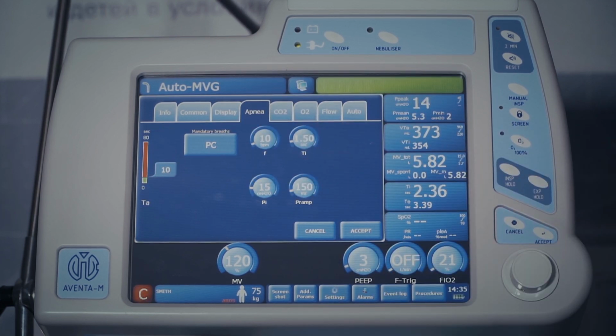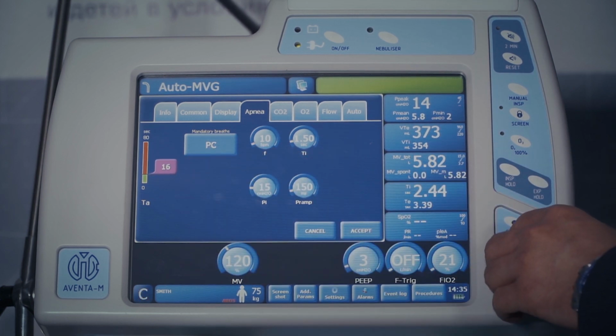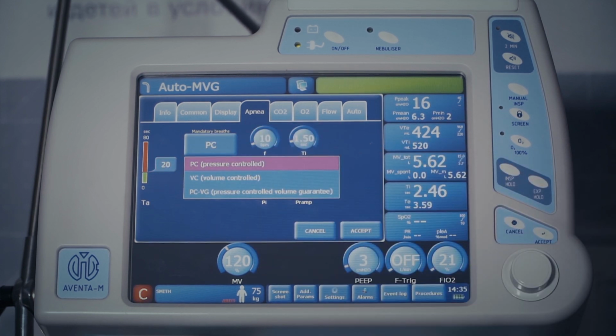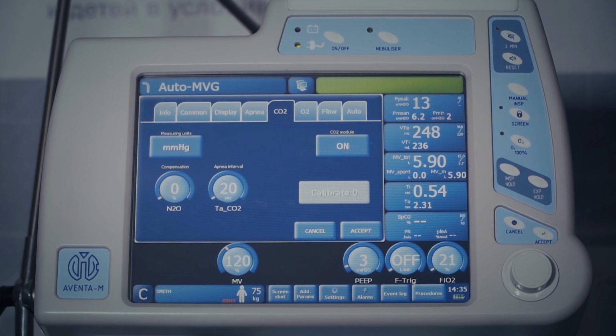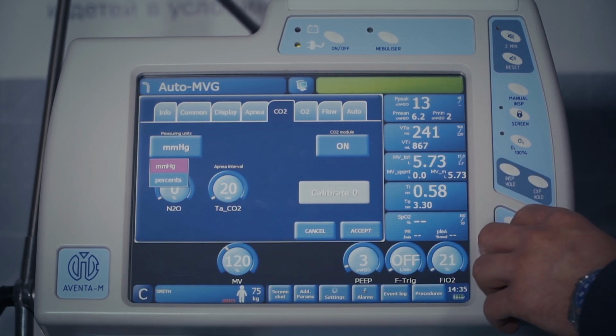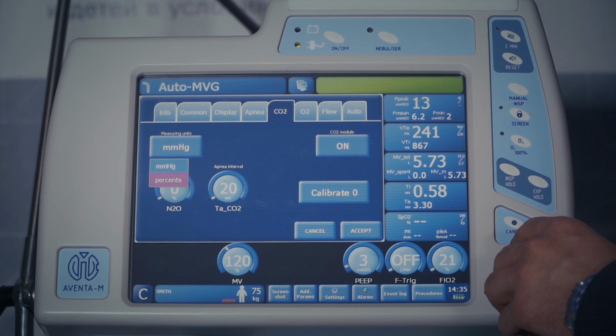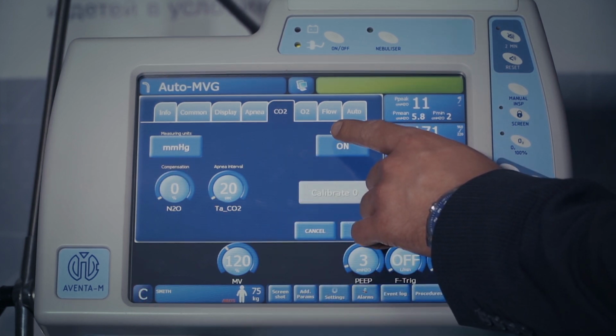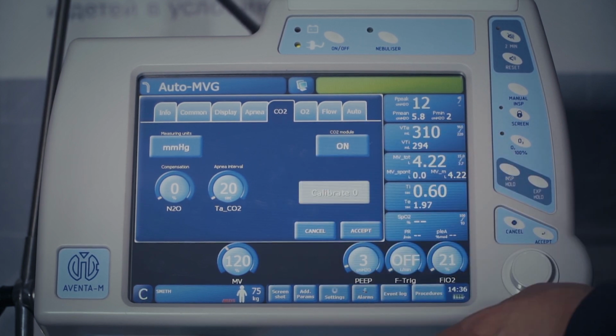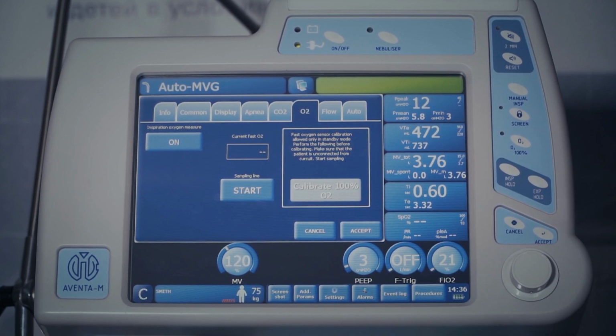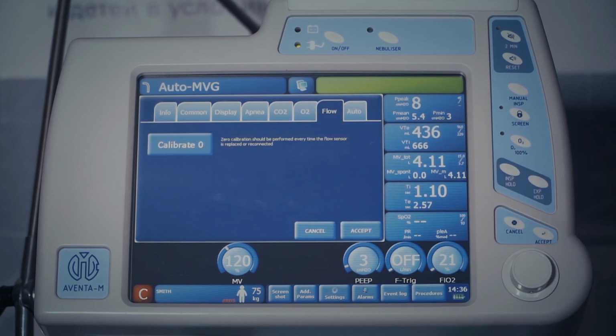Tab Apnea is intended for setting protective mode apnea as an additional one for the modes with spontaneous ventilation. Set the limit of apnea alarm actuation, type of mandatory breath, machine breath rate, and additional parameters. Go to tab CO2. Here, it is possible to switch capnography sensor on and off. Calibrate the sensor. Set CO2 parameter measurement in % or millimeters of mercury. In the last tab, Auto, it is possible to switch on automatic calibration of flow and oxygen sensors.